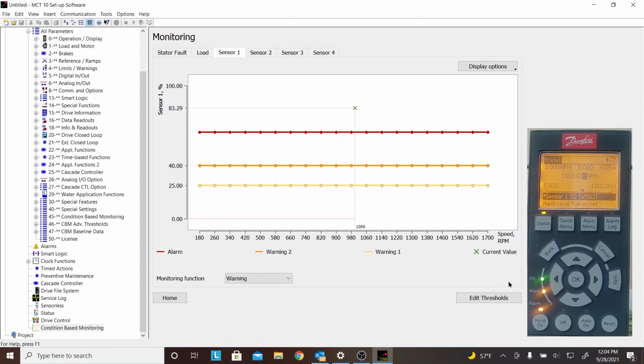You'll also notice down here in the keypad, besides the LCD display up here, the little warning light comes on as well whenever you hit these warning levels. So you can tie that to a relay. You can tie the alarm to a relay over the communication bus network, so it can be Ethernet, Profinet, Profibus, whatever. So this gives you a lot of flexibility. I'm just going to go ahead and set that back down, and everything will go away, and we're back in normal running conditions.